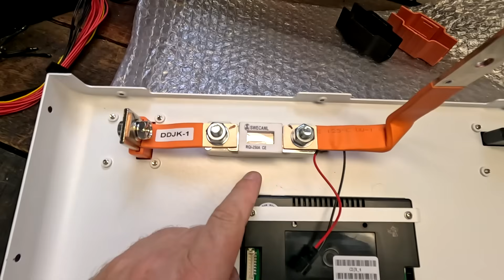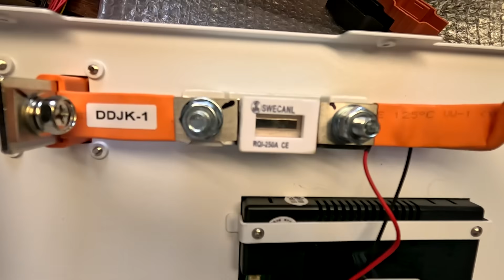And this was the fuse a bit in question, I would say. It says 250 amps here, but it neither says DC nor could I find any information. It's a SWECANL fuse. And EEL gave me the information that this one is rated for, I think, 80 volt DC and 20 kiloamps of breaking capacity. I couldn't confirm this information. I didn't find any information about this fuse here.